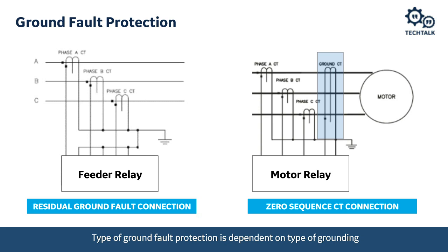So imagine if you have these CTs on the left on the phase are 300:5 CTs, and we have engineered the ground fault current at this facility with a grounding resistor or a grounding transformer, some mechanism like that, to a few hundred amps.